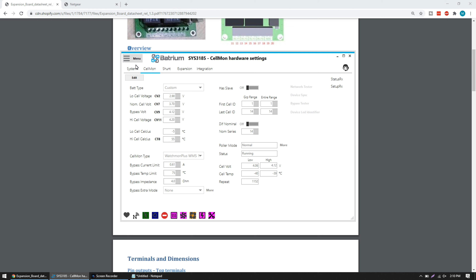With the Watchmon 5, there is no device sync needed. So you can go back to the chart and see it's no longer balancing. You'll notice at the top my temperatures are -40 and -37 because I have not plugged in the temperature sensors yet. Now we can go ahead and plug in the supply power so we're not relying on the USB connection any longer.